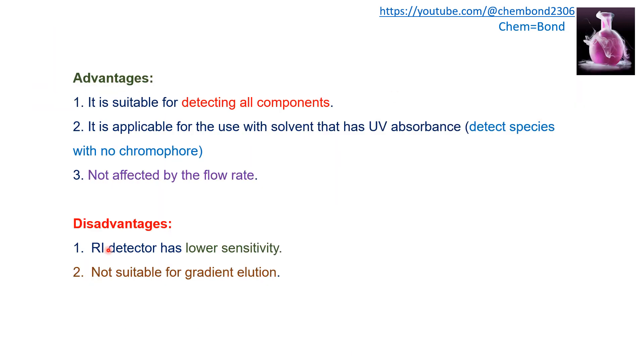Advantages and disadvantages of the refractive index detector: it is a bulk property detector so it will detect all components; it is applicable to solutes with no UV absorbance and can detect species with no chromophore; and it is not affected by flow rate. Disadvantages include lower sensitivity, and it is not suitable for gradient elution.